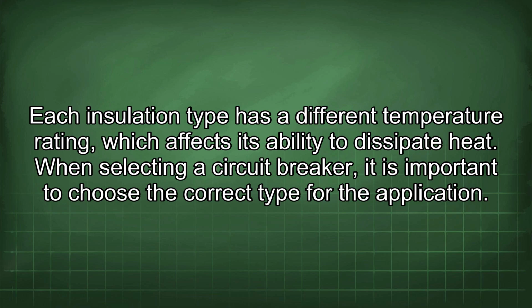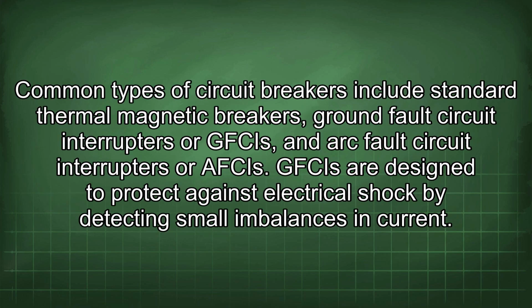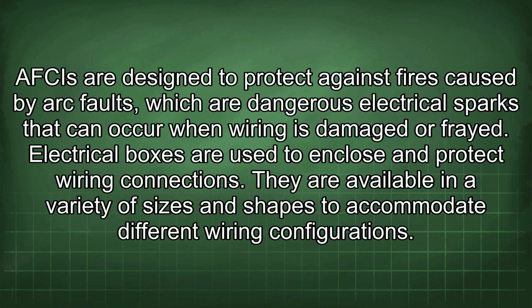When selecting a circuit breaker, it is important to choose the correct type for the application. Common types of circuit breakers include standard thermal magnetic breakers, ground fault circuit interrupters or GFCIs, and arc fault circuit interrupters or AFCIs. GFCIs are designed to protect against electrical shock by detecting small imbalances in current. AFCIs are designed to protect against fires caused by arc faults, which are dangerous electrical sparks that can occur when wiring is damaged or frayed.